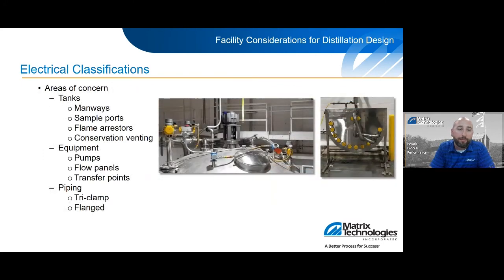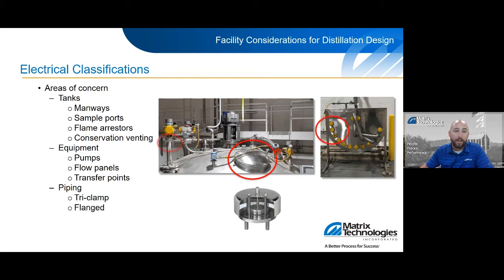Examples of areas of concern for electrical classifications would be your manways or your sample ports, flame arresters and conservation vents. Scott mentioned that earlier, and we just looked at it on the previous slide. This will vent your tank, and also in the event of some sort of fire inside the tank, that's a good avenue for the fireball to exit out of. You've got pumps and flow panels and transfer points. And then you've got your piping connections. You've got your tri-clamp connections, which are usually on your instrumentation or valves close to the equipment. And then you also have flange connections too, that could either be on your tank or on piping spool pieces that run through your facility.